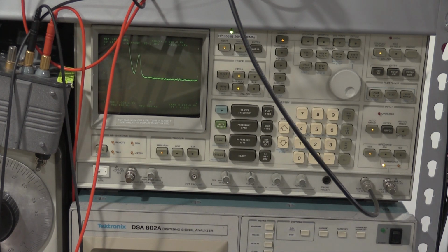This is still running. I do have the spectrum analyzer in max hold mode, which is showing me the worst case scenario. So as it does sweeps, it is showing me the highest level of signal that it is seeing, which is fine. I think I am at the limits of this spectrum analyzer, to be perfectly honest. I got better than specification, but a little bit worse than typical for the distortion at 1 kilohertz.